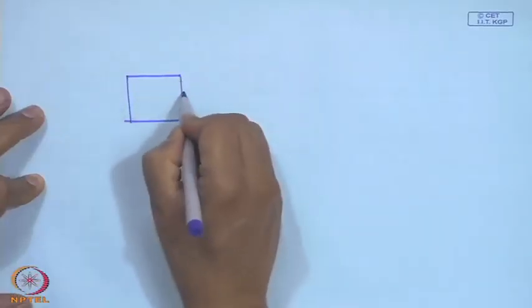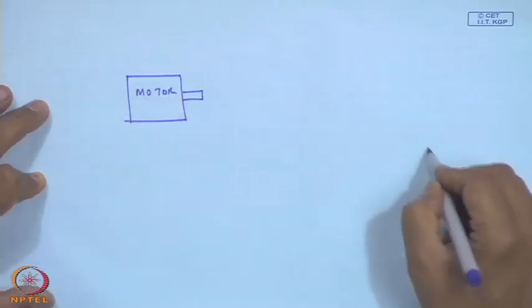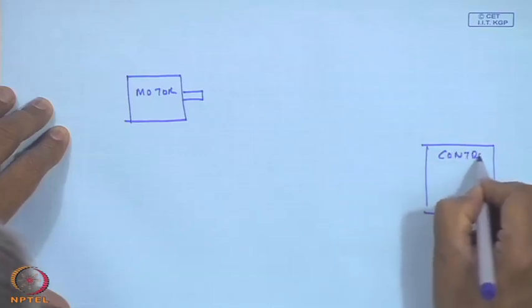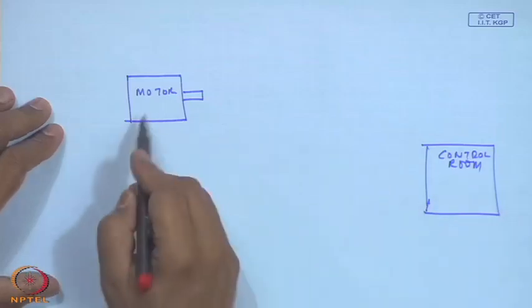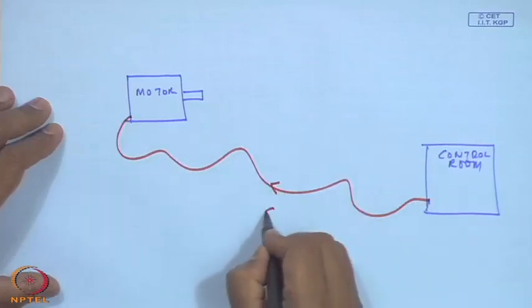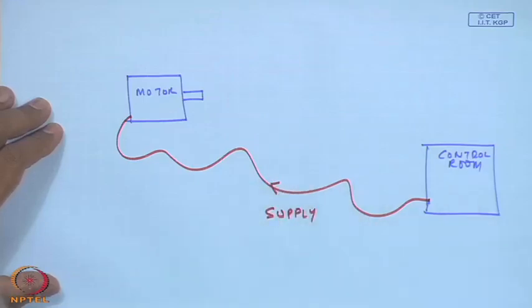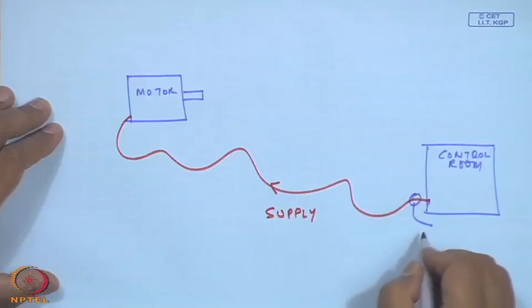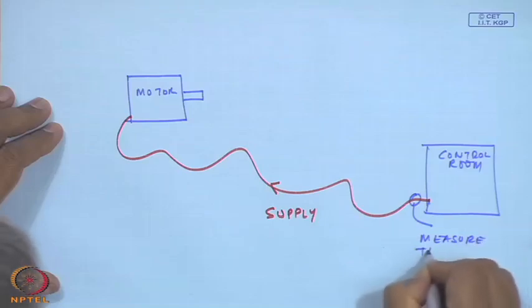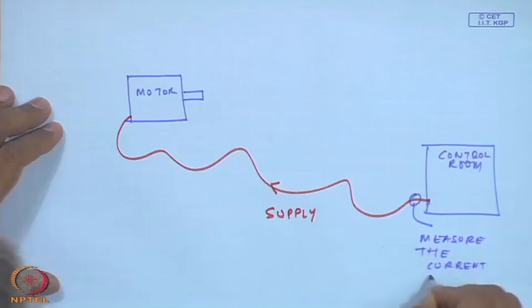That is why measuring and monitoring current has become a very powerful and convenient technique of monitoring motor faults. Imagine you are sitting somewhere in the control room, and an electrical motor is maybe miles away. All you need to do is lay a current conductor from your motor. So, you need not go to the motor. I'll tell you why and how. Suppose we have a motor, and you are sitting somewhere in a control room. Obviously, to drive the motor, it requires a supply, and the supply cable is maybe going from here. I have just drawn one conductor. So, very easily you can measure, at this end, the current waveform.